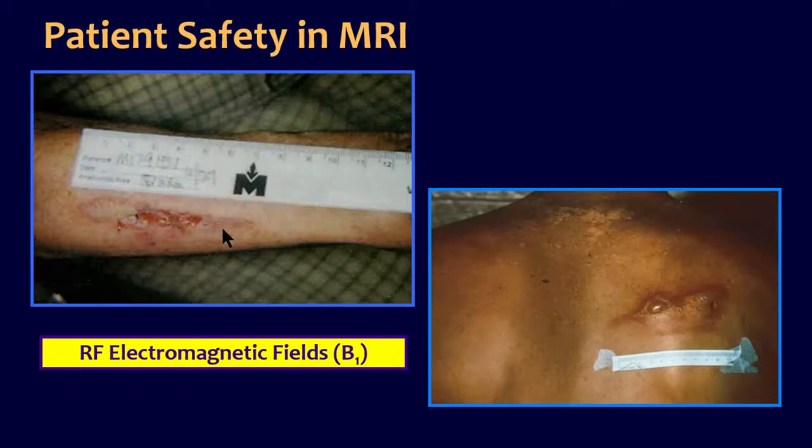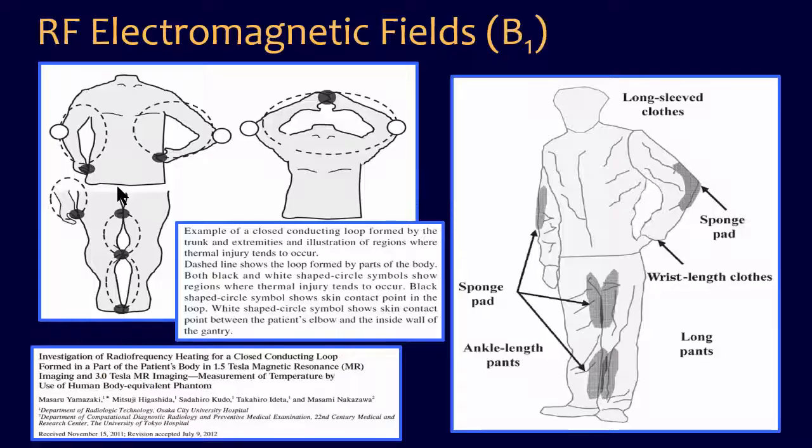Because if it does, you induce a current, it runs into resistance somewhere, either where the electrodes are or if it touches the subject a second place, and then that's when you experience a burn. Dr. Kugel also showed about this, about there being more emphasis on people being a conductor just with themselves. There was a story about a woman who was having a breast scan with her hand against her forehead. A breast scan, she was on her stomach, and she received a burn between her hand and her forehead.